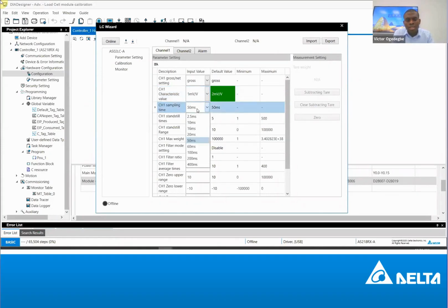And then the sampling time, this is the time it will take for the load cell module to sample the analog signal coming from the sensor. So what the sensor is giving you, how long will it take to read it? So you specify it. It's advisable, if your application permits, to set a bigger time. You can see that the default is 50 milliseconds. It's in the middle. If you set a bigger one, then the module has enough time to sample the sensor data and give you a steady and stable value.